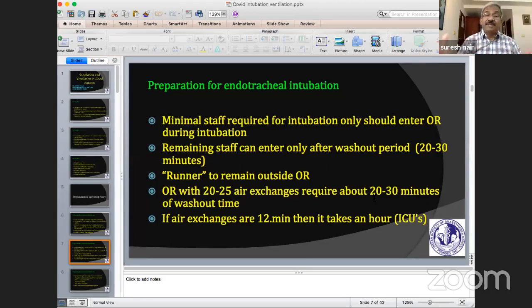The remaining staff enter only after a period of 20 to 30 minutes. Why 20 or 30 minutes? Because when we use a HEPA filter in the room, the fresh gas flow or air exchange is about 20 to 25 per hour, which is normal or standard for any operating room. It takes about 20 minutes for the washout of the gas or air in an operating room.